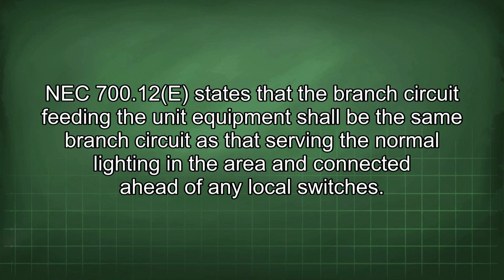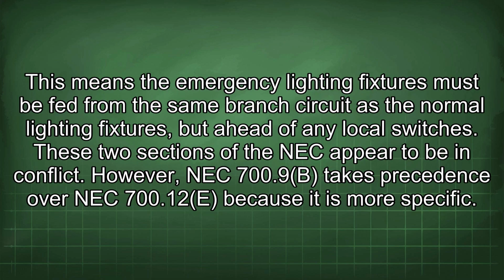NEC 700.12(E) states that the branch circuit feeding the unit equipment shall be the same branch circuit as that serving the normal lighting in the area and connected ahead of any local switches. This means the emergency lighting fixtures must be fed from the same branch circuit as the normal lighting fixtures, but ahead of any local switches.